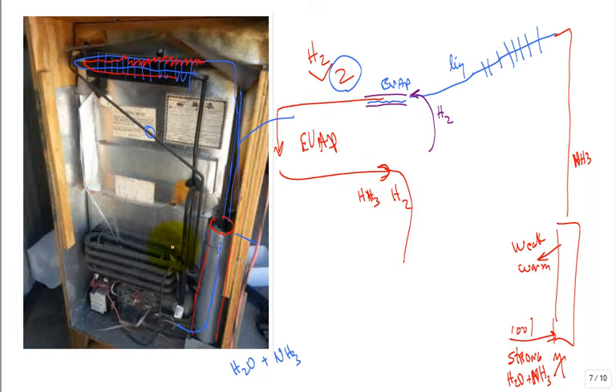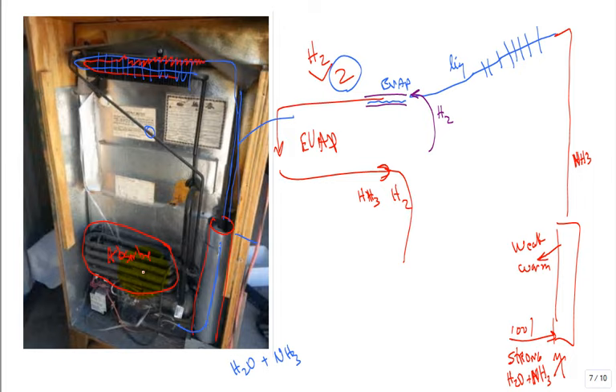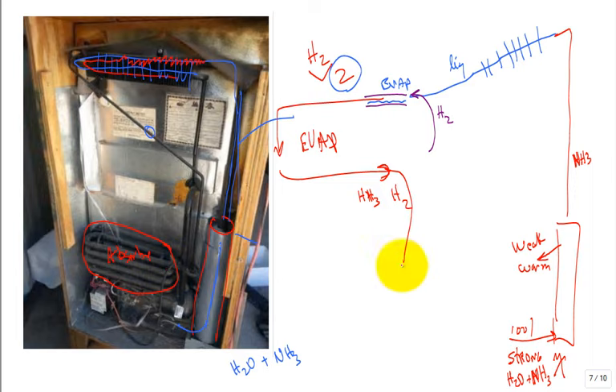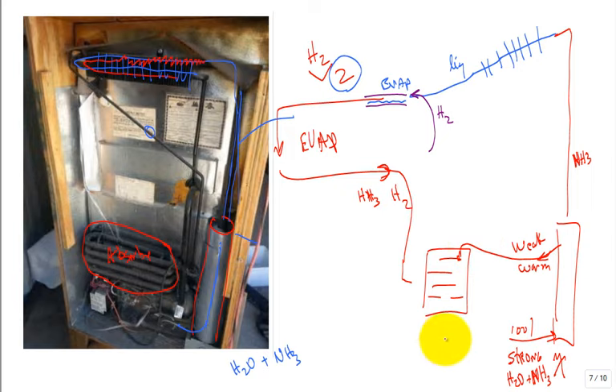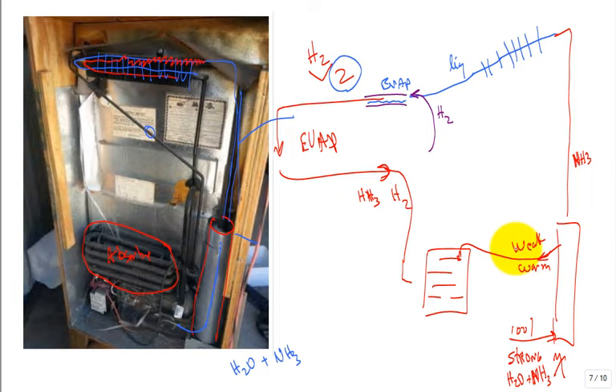I've got ammonia, I've got hydrogen. You put it through this big contraption over here. What's this doing? It's an absorber. I've got ammonia flowing one way, hydrogen flowing another way, water flowing one way. This is not that easy to describe. It's thin, so I'm rejecting some heat to the surroundings. This weak solution comes in and it's percolating over, being cooled as it's flowing through. As the water is cooled, it can absorb some more ammonia.